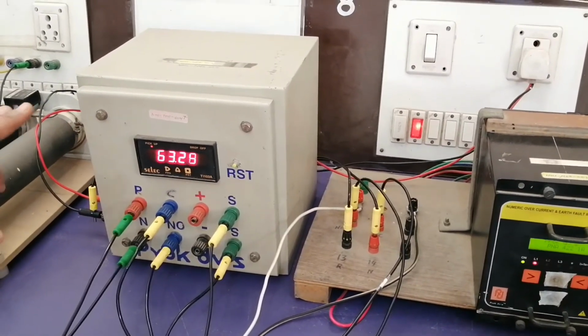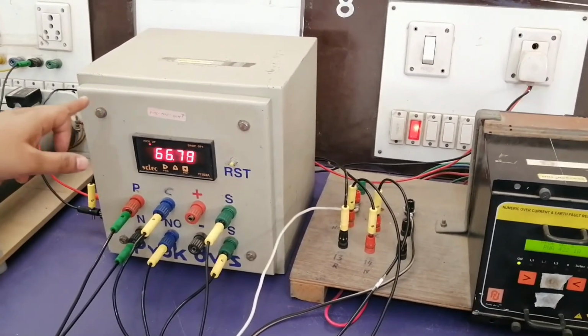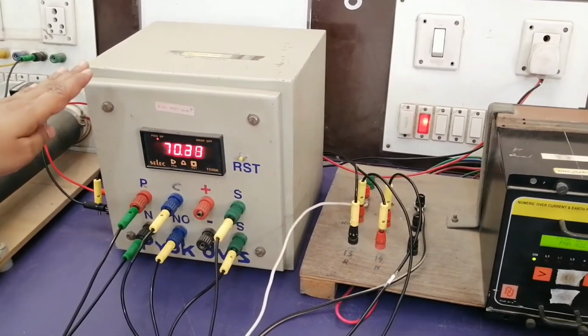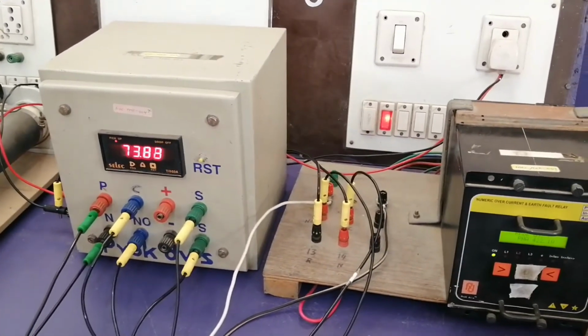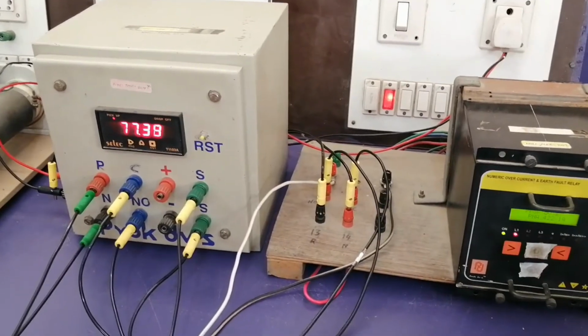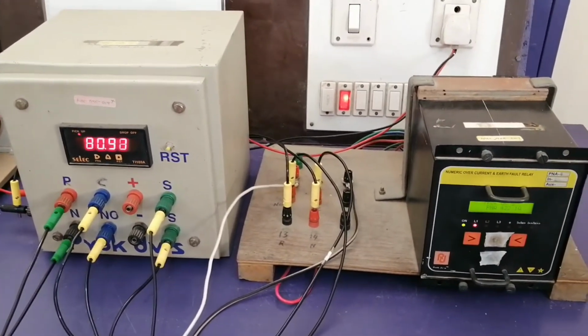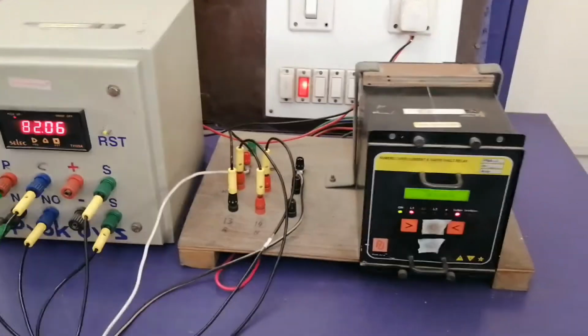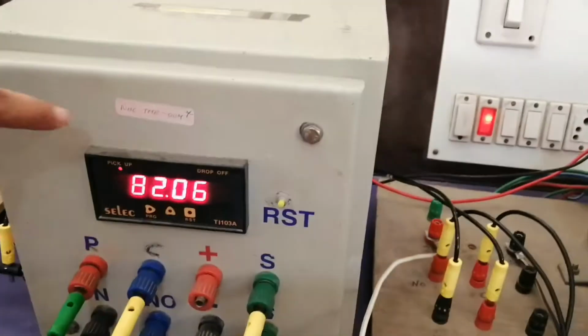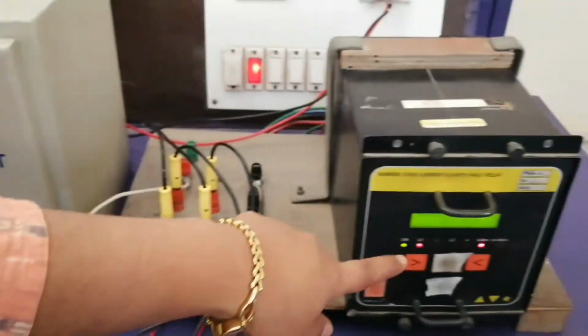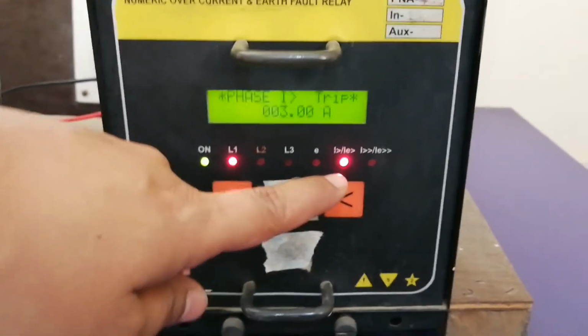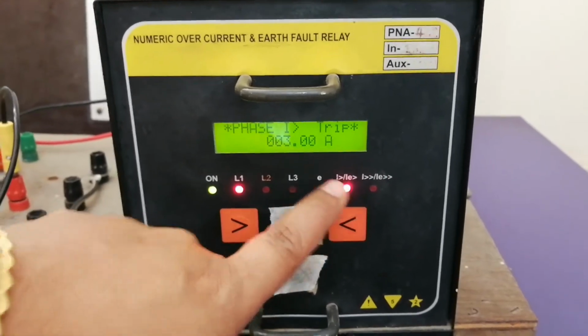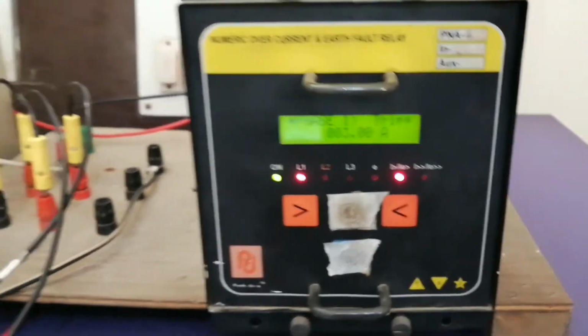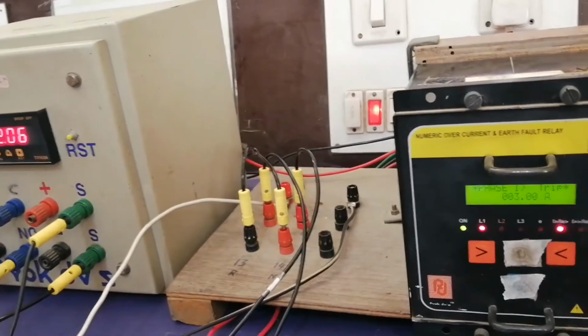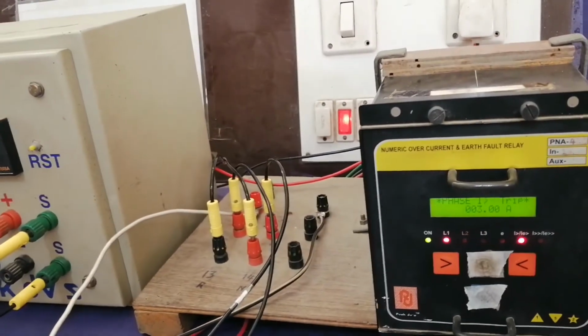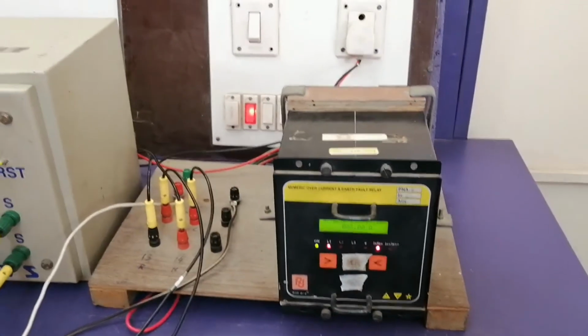So what you have to do is, just wait till your timer reaches the normal condition. Wait and watch the timer till it reaches the normal condition. Now you can observe here, 82.06 seconds is the time taken for 3 ampere current to reach the relay box. You can see here, L1 has holded, and here one more dot is indicated. The meaning of this is, at 3 ampere the time taken is 82.06, but this is not the actual time. The actual time is, when the fault occurs, the timer should start and relay should start.